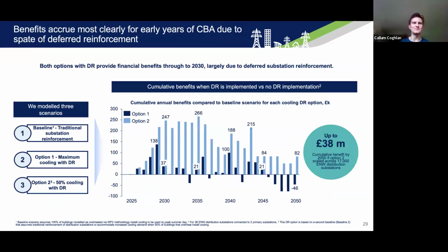Brilliant, I can come in here. So we fed the network impacts that Del's just talked through into a high-level CBA, in which we annualized the required transformer reinforcements and the reinforcement costs, and compared those with the cost of procuring cooling DR to understand the potential benefits that DR could offer to the network. And the graph on this slide shows that cumulative benefit for two different DR options across those 36 distribution substations that Del just spoke to. And in this case, DR is applied for 2 hours coincident with the substation peak load. And the two options here, you can see they align with the DR scenarios that Del described on the previous slide.